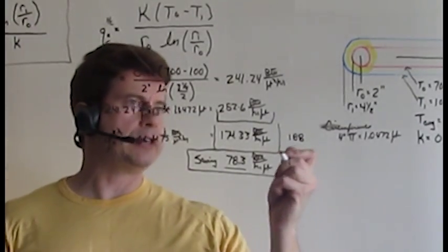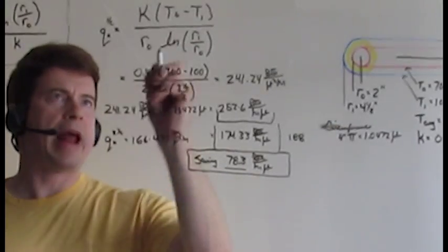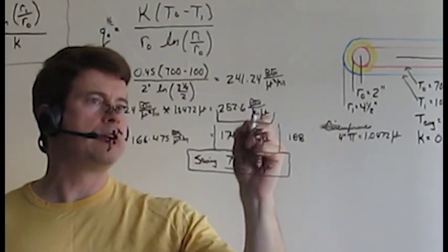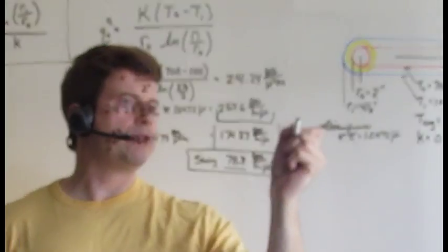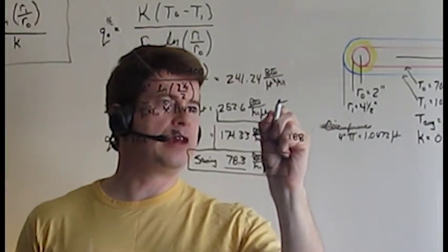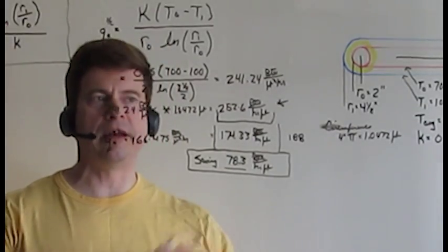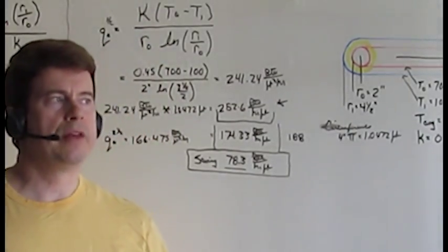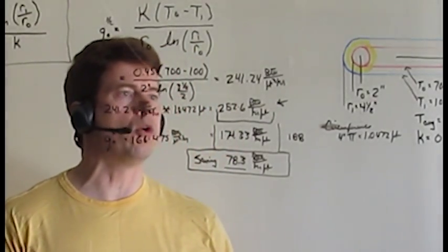Certainly another justification with this is if you go to the Owens Corning site, they don't even have specifications for 1.5 inches of insulation on a 700 degree line. So actually this is theoretical and is probably a much higher heat loss, simply because they really haven't designed these numbers and equations to fit into such a thin insulating category.